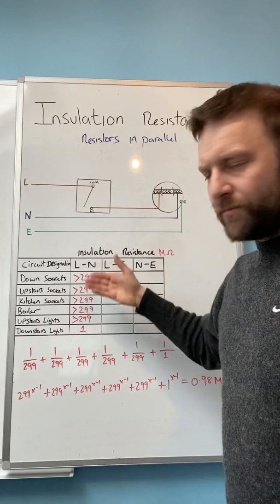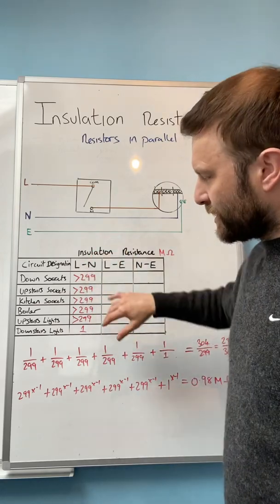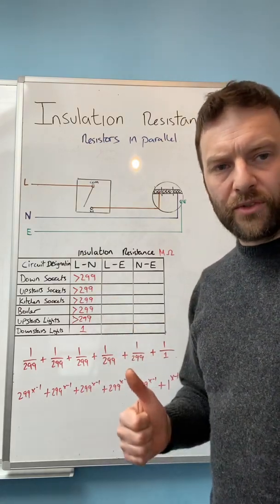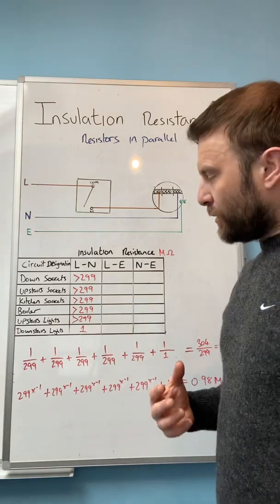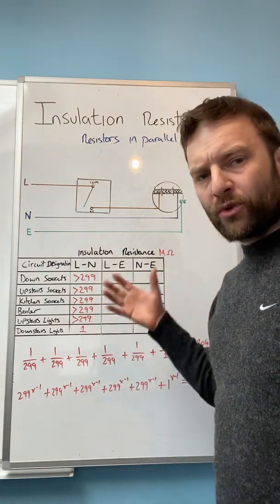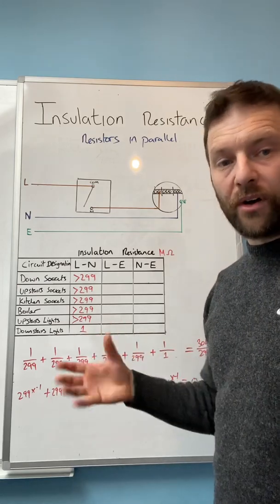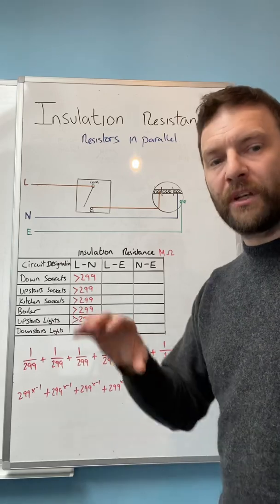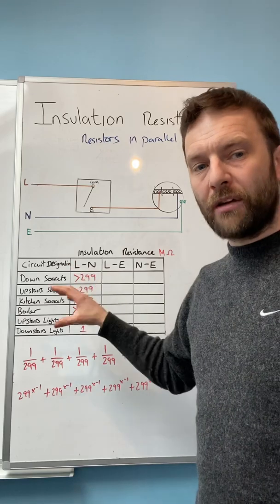And then what I've done is I've just made up some manufactured results between live and neutral for insulation resistance. On five of the circuits I've got greater than 299 so we're absolutely good to go. And on one circuit I've got one mega ohm. Now what does that mean, does that mean that's a pass or a fail? Because one mega ohm I could say that that is a pass for that circuit but according to BS 7671 it's for the whole installation and the only way to work that out is to do resistors in parallel.